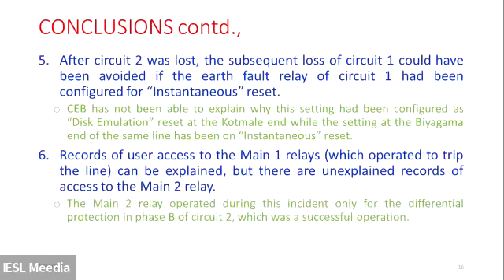corresponding to the neutral current rise, right? The relay may have picked up the earth fault, but that high current came below the threshold level after 288 milliseconds. Because the reset settings were configured to disk emulation, it didn't react instantaneously. So our conclusion is that it could have been avoided. Of course, this may have to be trialed if this was set to instantaneous. One other reason why we are saying so confidently is that at the Biyagama end, it is in the instantaneous reset.